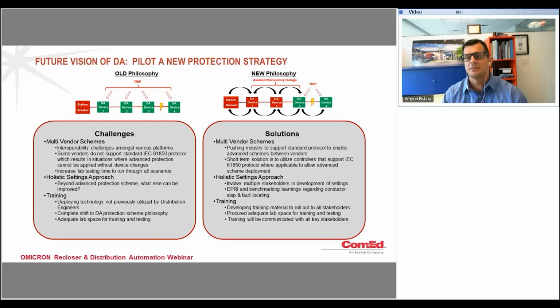Now we want to shift our attention to our new philosophy on the right side, where we want to pilot a communication-assisted advanced protection strategy. This has communication-assisted tripping, which isolates only the faulted segments, which results in our MAIFI reduction. Also, the high speed would help with reduced fault current escalation and arc flashes. As for the communication-assisted restoration, this has faster tie closing for reduced momentary durations. This scheme would communicate through our fiber optic cables, which has less than 1 cycle latency.